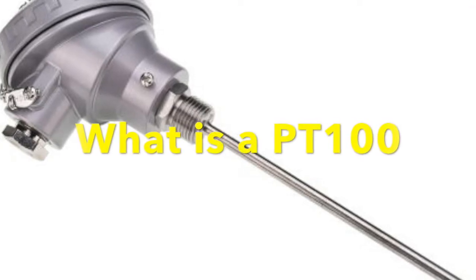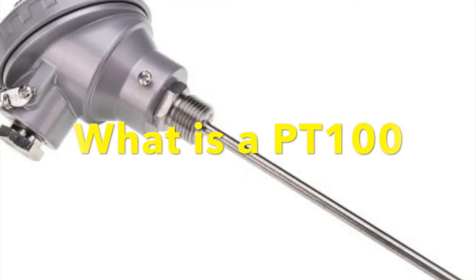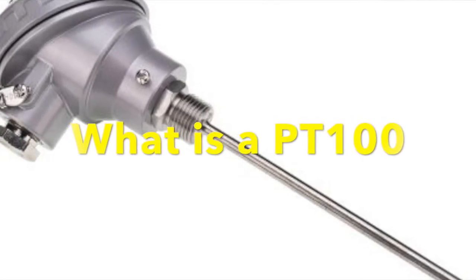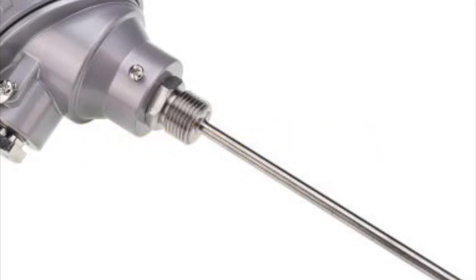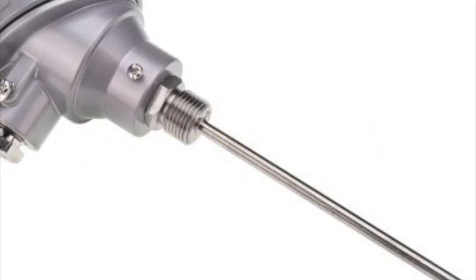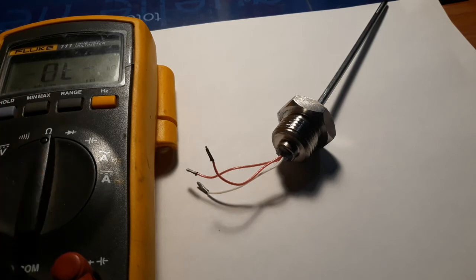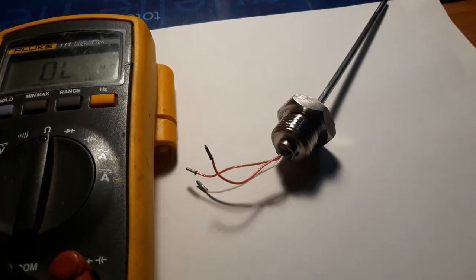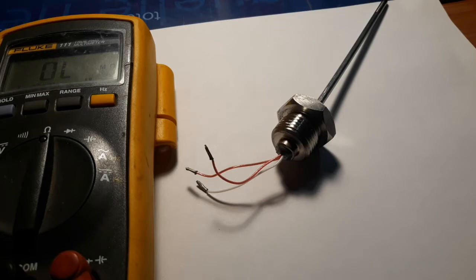A PT100 is a temperature sensor based on the physical properties of platinum. The sensor is based on the ohm variation with respect to temperature. At zero degrees Celsius, the probe has an electrical resistance of 100 ohm.